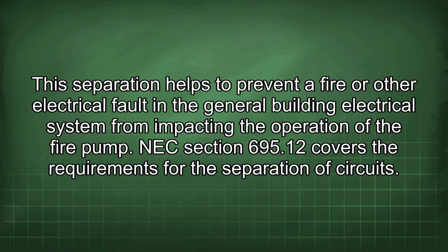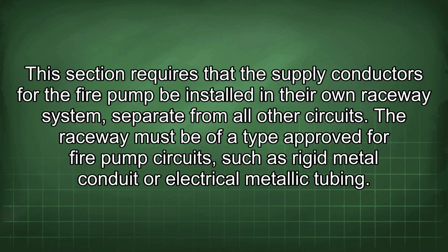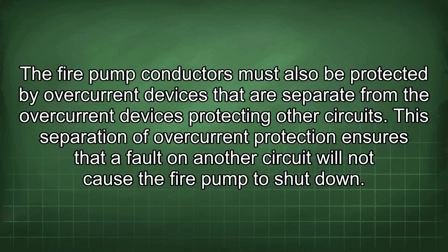NEC Section 695.12 covers the requirements for the separation of circuits. This section requires that the supply conductors for the fire pump be installed in their own raceway system, separate from all other circuits. The raceway must be of a type approved for fire pump circuits, such as rigid metal conduit or electrical metallic tubing. The fire pump conductors must also be protected by overcurrent devices that are separate from the overcurrent devices protecting other circuits.